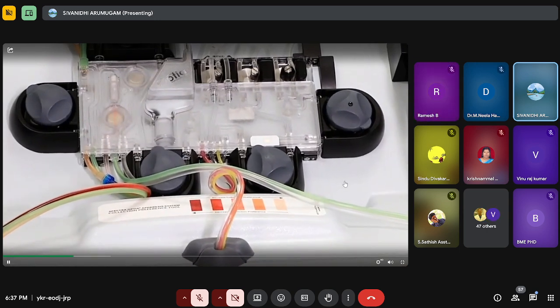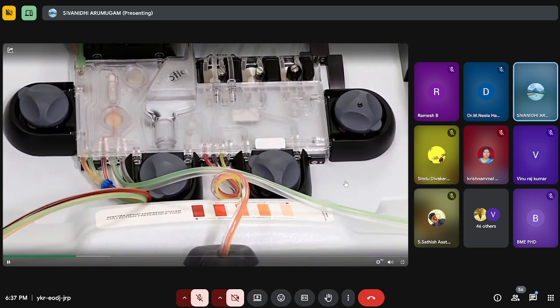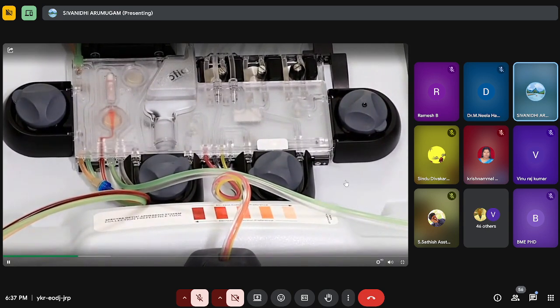When the chamber is full, the system triggers a collection phase. Here you can see this pump is rotating, right? The accumulation cells. You can see this is rotating and this is rotating. It means it is collecting blood and adding AC to it. So the blood with AC is now coming into this cassette, and from the cassette, it is going to the centrifuge.